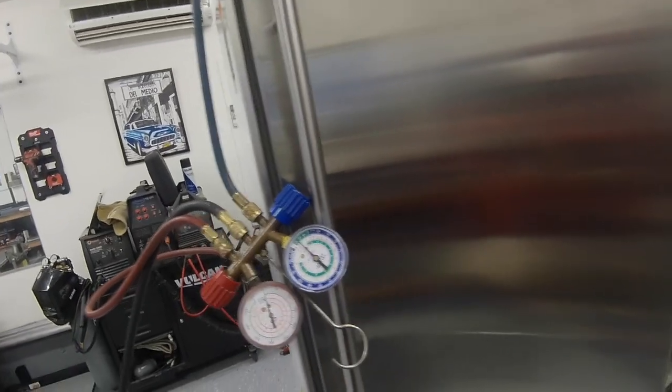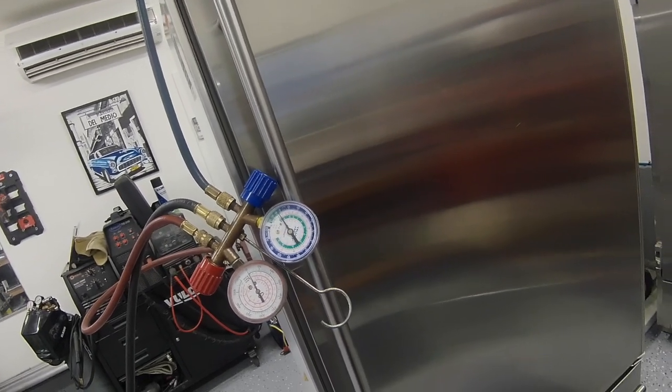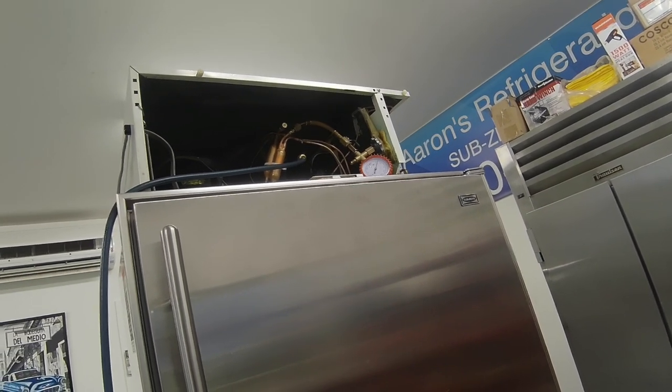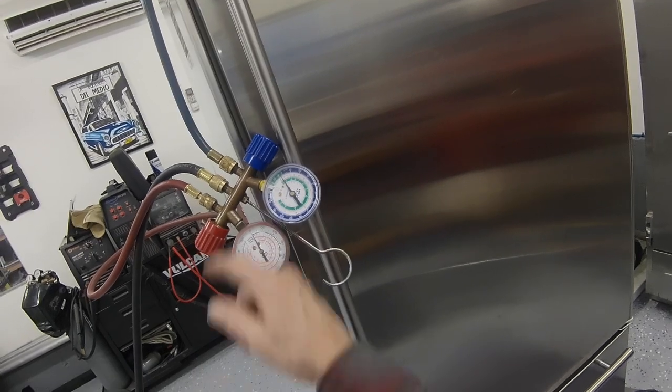Alright, I'm going to let this sit. It's now 4:30 in the afternoon. See how long it takes for that to start moving because I know it will come up. So a few minutes have passed, three minutes or so. The pressure is starting to come up and the head pressure is starting to come down a little bit, not much. There's a couple degrees there.